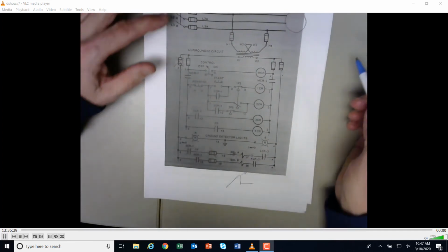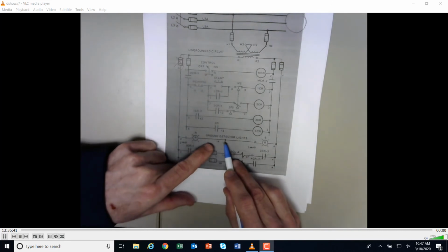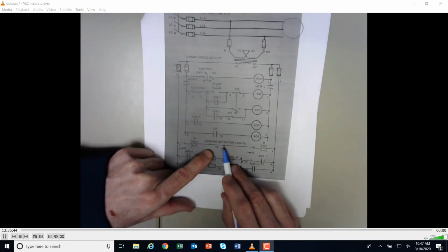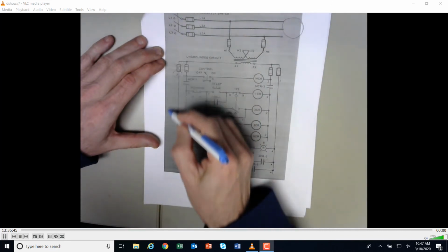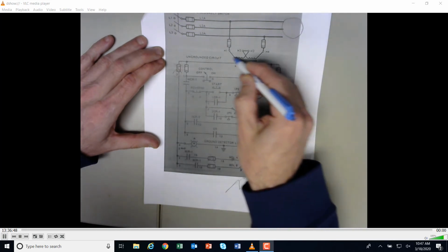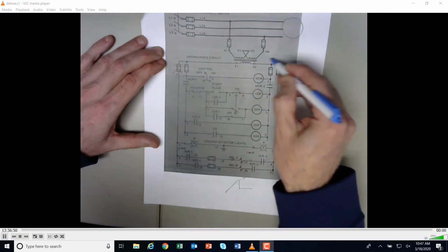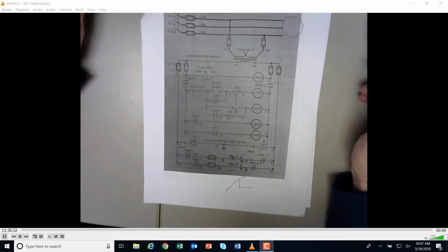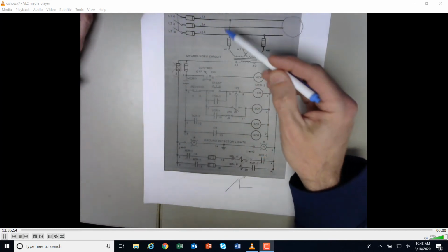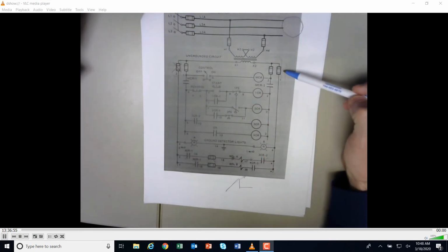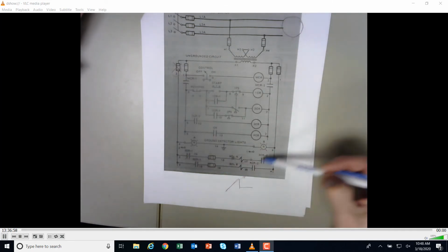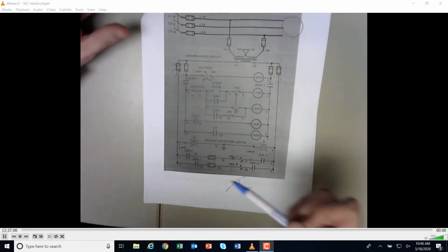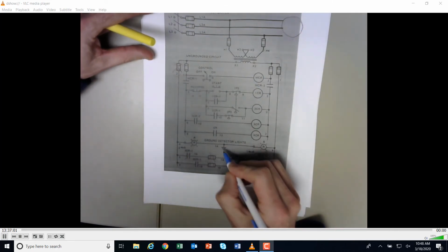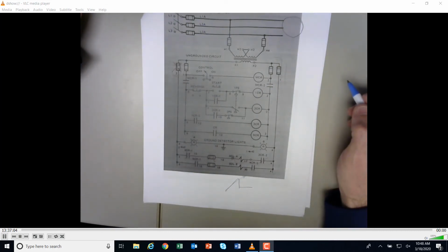So here's my ground detectors. In an ideal situation, let's say this whole control panel right here was isolated. It was not part of the electrical system at all. It's not grounded to it. Let's say it was mounted on rubber, so that this was its own standalone item, and that we were grounded here to the panel itself.